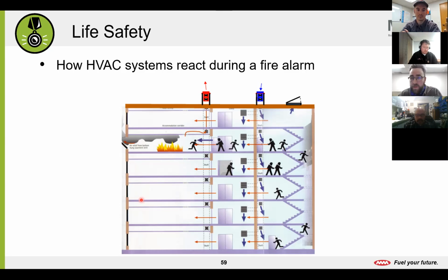Obviously, some stuff is going down on the 5th floor, right? We have a fire that broke out in the corridor. And your fire system, your sensors, your fire panel, that's all tied to HVAC equipment that is meant to serve your building in the event of an instance such as this. Looking at this picture here, we have this red guy on the top. This is what's called a corridor exhaust fan, and it does exactly that. In the event that we do have an issue, its job is to kick on and start pulling air out of that space. Over here, this blue guy, this is what we call a stairwell pressurization fan, and just like the name implies, it does the opposite of our exhaust fan, and it's supposed to positively pressurize our stairwell.